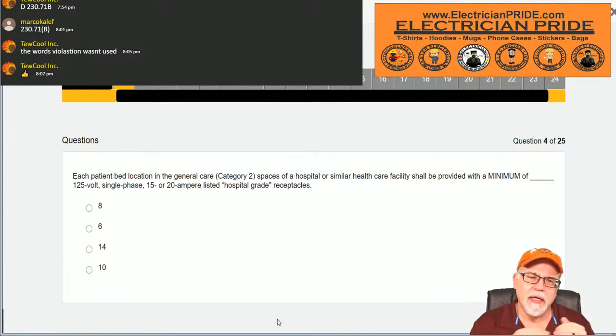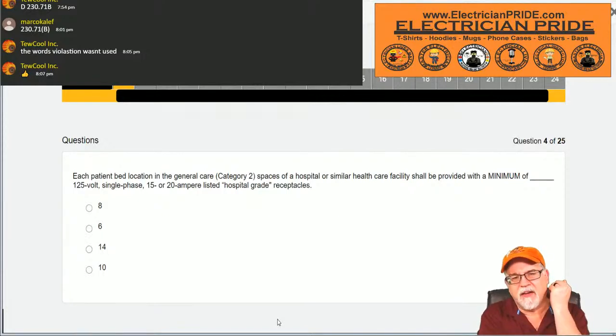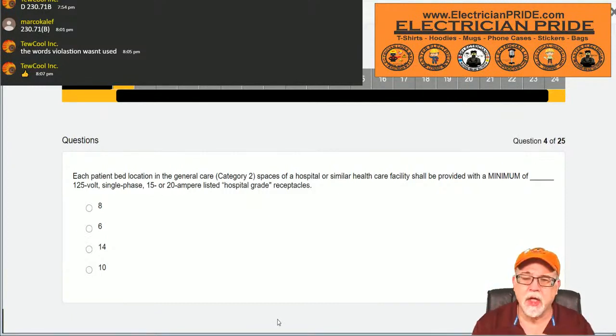Now, next one: each patient bed location in a general care, which is now called a category 2 space, in a hospital or similar healthcare facility shall be provided with a minimum of blank 125-volt single-phase 15 or 20 amp listed hospital-grade receptacles. Okay, what are the triggers here?